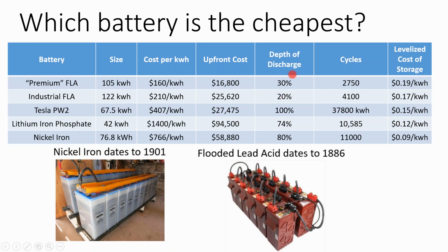Instead, what you get is a chart that tells you how deeply you can discharge the battery and how many cycles you'll get at that level of discharge. What's kind of interesting about the higher end lithium ion technology is that the monitoring systems are much more robust. And when we think about how batteries corrode, the depth of discharge in cycles is a lot more ambiguous than just giving it a hard kilowatt hour number, which more appropriately reflects its usage.